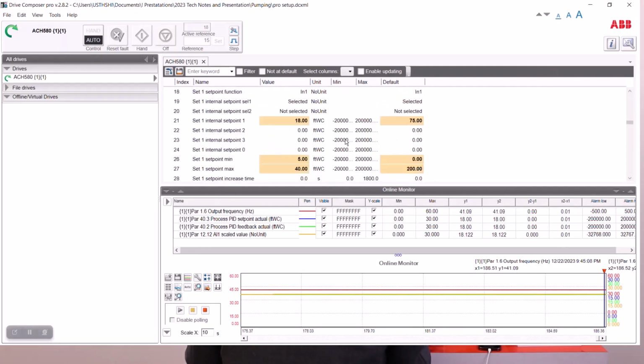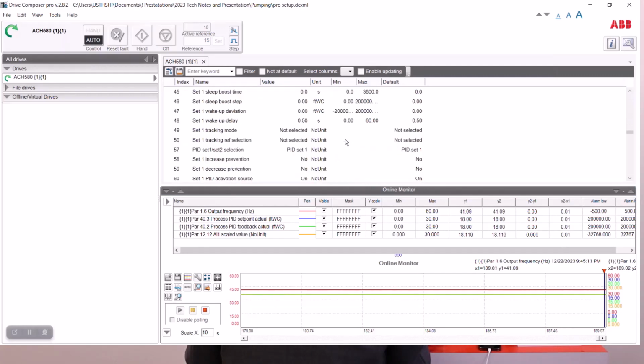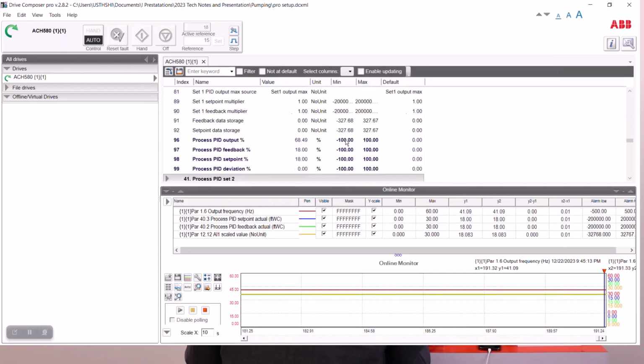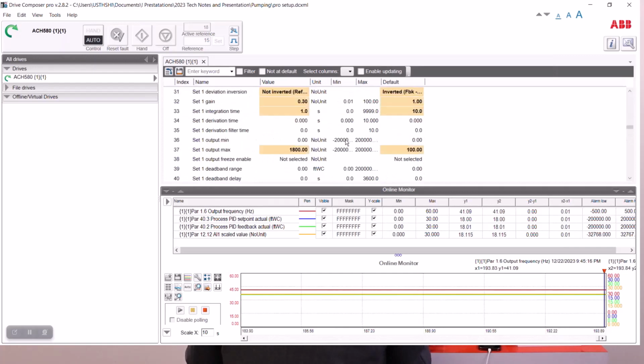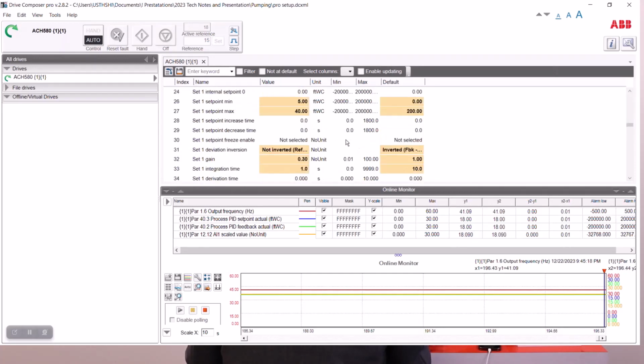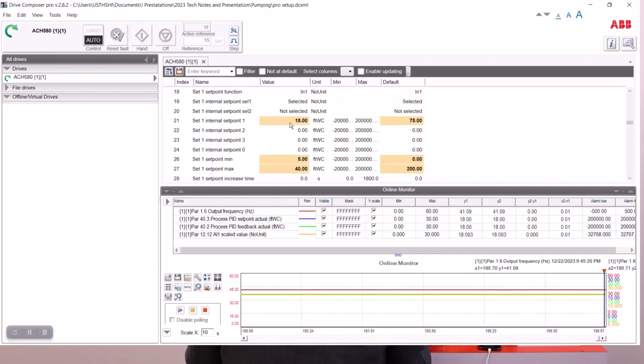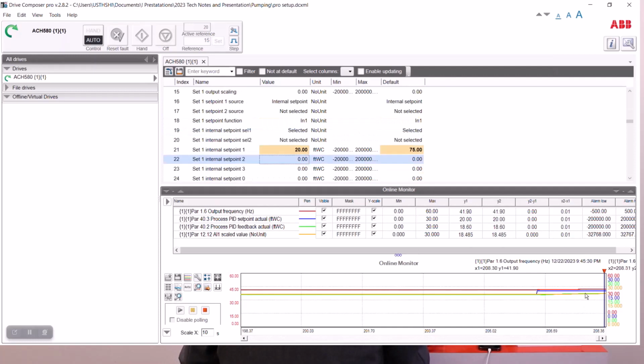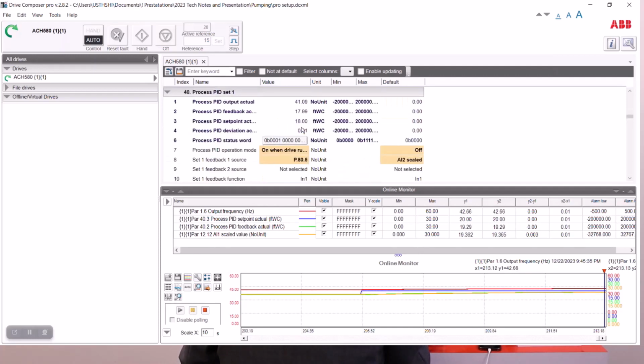And as I can show you, I can go into the system and I can change my set point. And by changing the set point, I can change the way the system's run. So here's my internal set point. If I change that, let's push it up to 20 feet. So I'll go to 20, enter. At this point, there's my jump right there in the blue line. The drive is speeding up. It's trying to stabilize out at 20 feet. We're seeing 19 feet here. Here's 20, and it's starting to stabilize out.